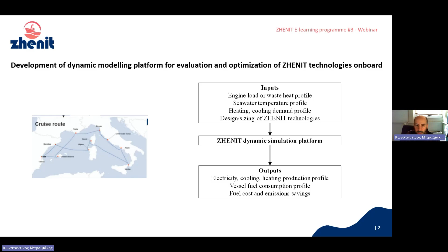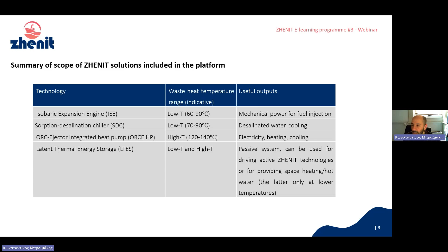I remind you that in this platform we incorporate four ZHENIT technologies. We have three active technologies: the isobaric expansion engine, the sorption desalination chiller, and the ORC ejector integrated heat pump, which were presented in the previous presentations. Then we have one passive technology, the latent thermal energy storage system. Each technology has a specific operating temperature range. It's important to highlight that the isobaric engine and the sorption desalination chiller operate with lower waste heat temperatures, from 60 to about 90 degrees Celsius, while the ORC operates at a higher temperature that can reach up to 140 degrees. The latent thermal energy storage is, in principle, a more flexible technology because we have different PCM materials, and depending on the desired temperature level, we can select the appropriate material.